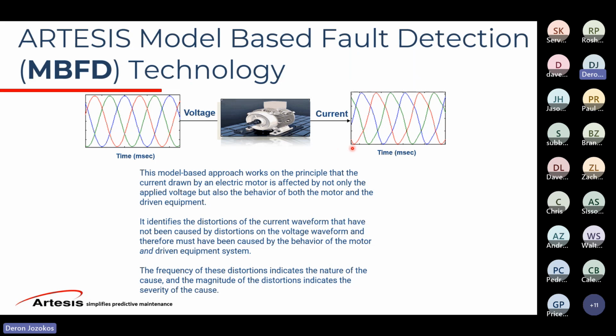So if we're only looking at the current, we could be fooled into thinking we're getting an alarm based on the frequency of these distortions on the voltage side. Maybe it's the same frequency of a bearing or a misalignment. So what the system does is it identifies all of those distortions on the voltage side and filters them out, so that the only thing left that can cause these little blips on the current side would be actual defects from the machinery itself.